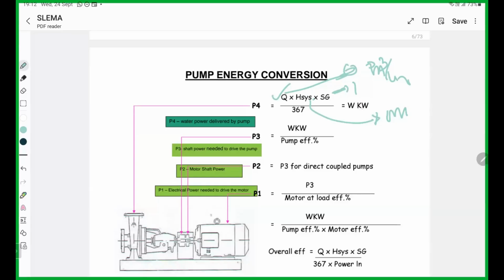Then it is in W, right? A very simple equation: flow rate into H, where the flow rate should be in cubic meter per hour, and H should be in meter. Then specific gravity of water is 1. Then divide by 367. Then we can calculate the water power out. In any case of a centrifugal pump, if you know the flow rate and the head, then we can calculate the power output of the pump. Then if we divide by the pump efficiency, we can calculate the shaft power, the pump input power. Generally, it is direct coupling. Almost we can consider it as 100% efficiency. Then in direct coupling, P2 equals P3.